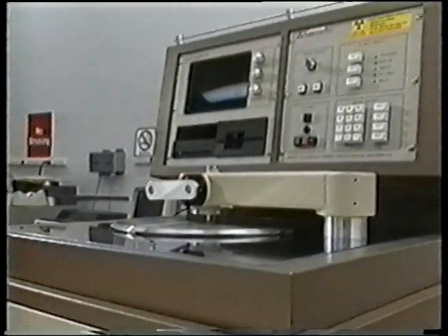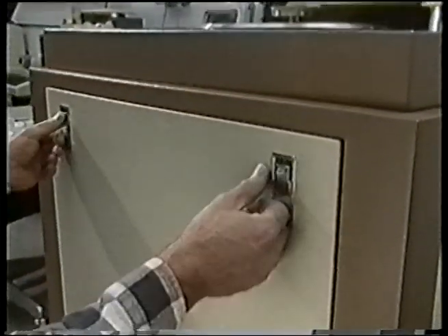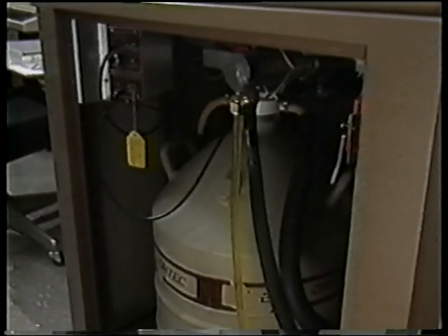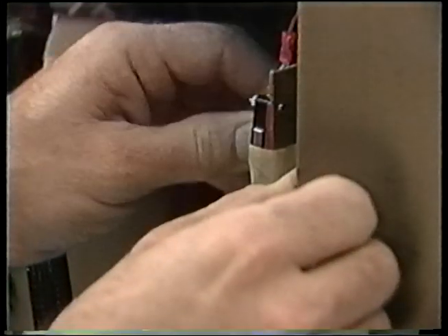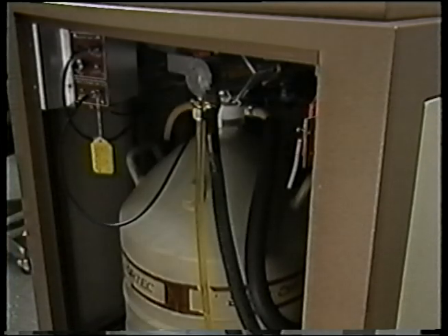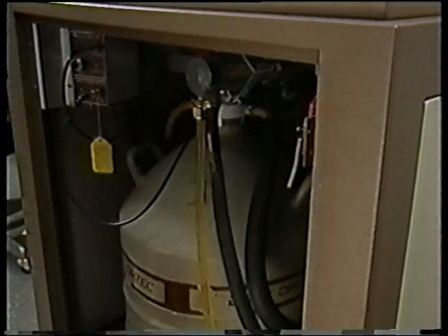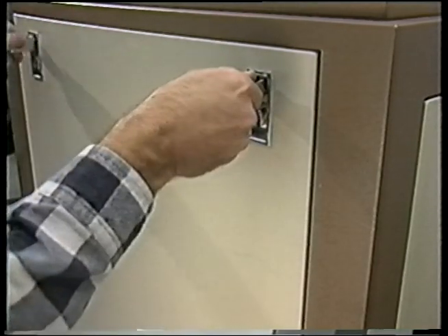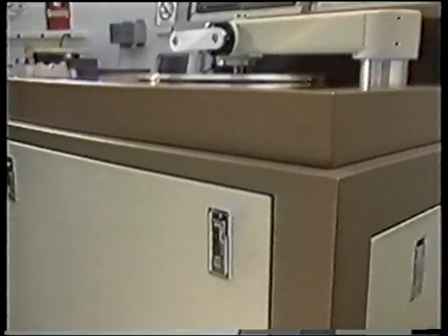On occasion, interlocks may need to be defeated by authorized personnel for equipment maintenance. This is the only time an interlock should be defeated. Even when an authorized defeat of the interlock takes place, a hazardous situation can be created. If these situations are not properly controlled, an operator's safety may be jeopardized. Procedures and practices must be established to ensure that equipment requiring maintenance is returned to its safe state.